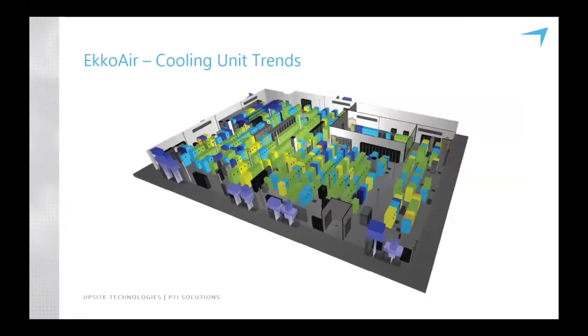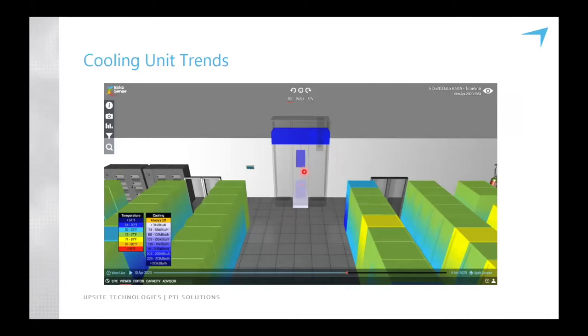When you look at this, you can start to do some very sophisticated things. This image shows the trends of the cooling units. So each of these cooling units has a histogram that represents the amount of time over the last 24 hours that this cooling unit has spent at different levels of cooling. And so you can see very quickly by looking at these histograms what cooling units are providing the most cooling and which cooling units are running idle. The software utilizes that information to make recommendations.